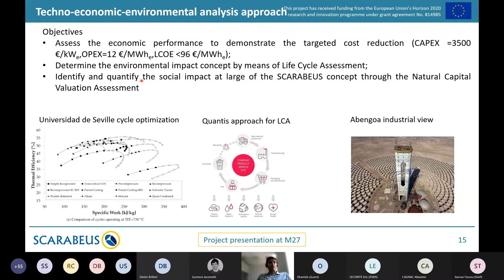From the modeling point of view, it was demonstrated that CO2 blends can achieve an efficiency above 50%, assuming 35 degrees C ambient temperature and 700 degrees C maximum cycle temperature. The key point is that this fluid should be capable of condensing at temperatures below 60 degrees C.